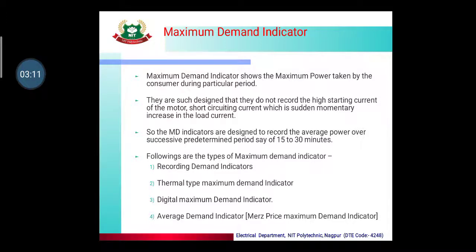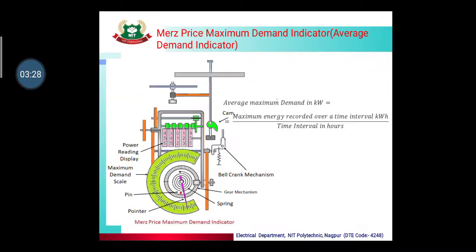There are basically different types of maximum demand indicators: recording demand indicators, thermal type maximum demand indicators, digital maximum demand indicators, and average demand indicators. The average demand indicator is also known as the Merz-Price maximum demand indicator, and its diagram is shown here. The formula for average maximum demand in kilowatts is: maximum energy recorded over a time interval in kWh divided by the time interval in hours.